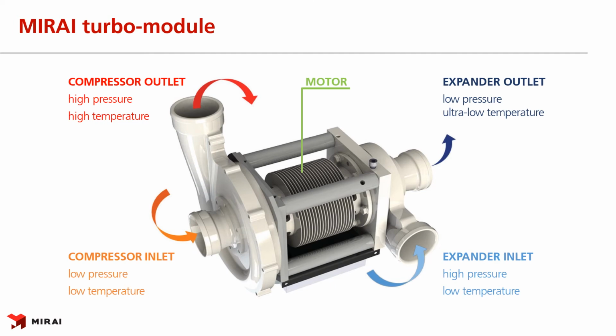As you can see on the picture, it is a very compact part. It is possible because the compressor and expander are located on the same shaft with motor between. With this design, we can save up to 30% of energy consumption compared to vapor compression systems used in the same applications. And why is that? In layman terms, when the air goes through the expanding process, it helps the motor to save energy to power the compression process, because both expander and compressor are located on the same shaft, as I mentioned before. So in conclusion, we can say that the expander work saves the compressor work with such design.